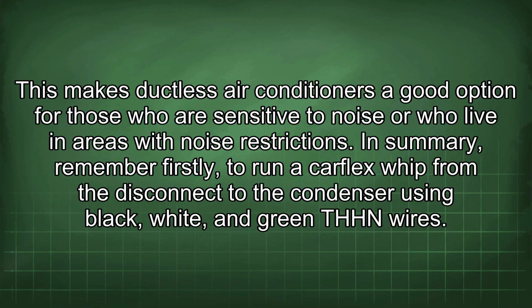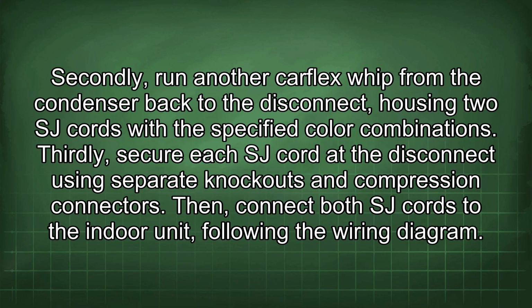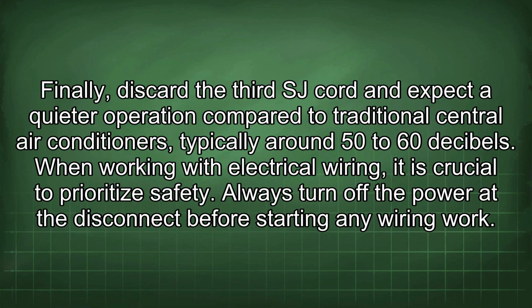In summary, remember firstly, to run a carflex whip from the disconnect to the condenser using black, white, and green THHN wires. Secondly, run another carflex whip from the condenser back to the disconnect housing two SJ cords with the specified color combinations. Thirdly, secure each SJ cord at the disconnect using separate knockouts and compression connectors. Then connect both SJ cords to the indoor unit following the wiring diagram.